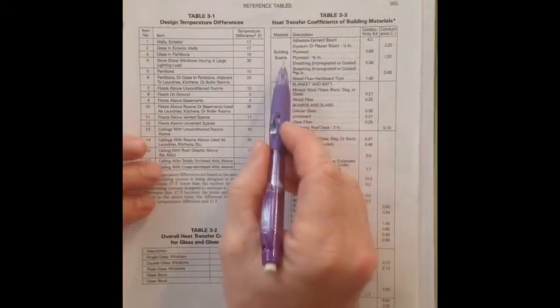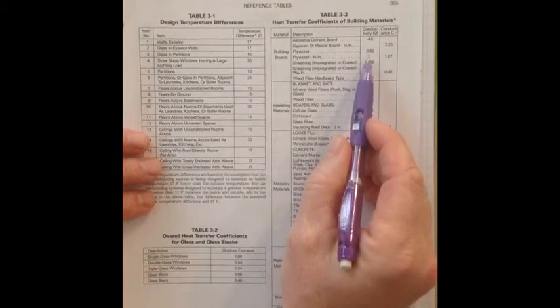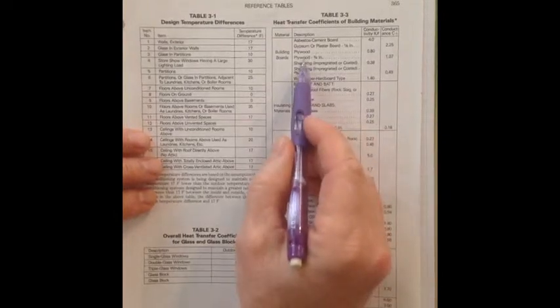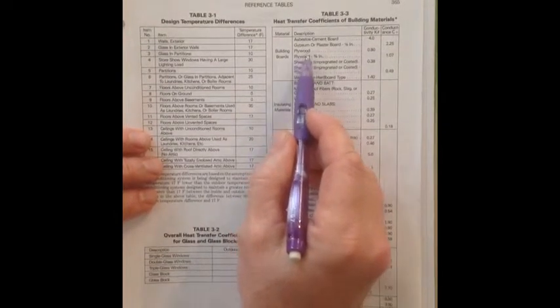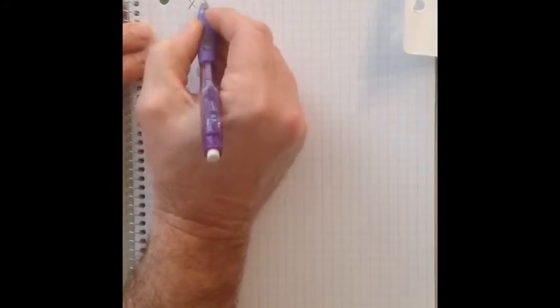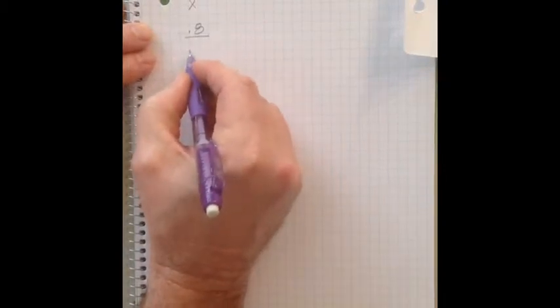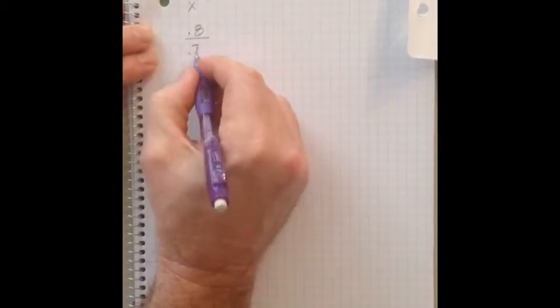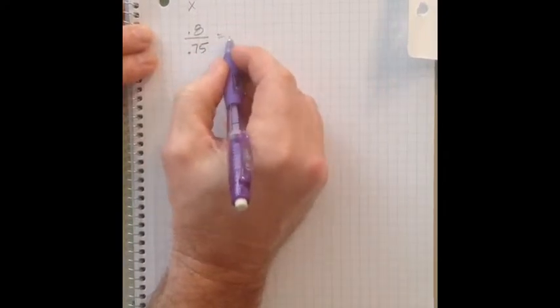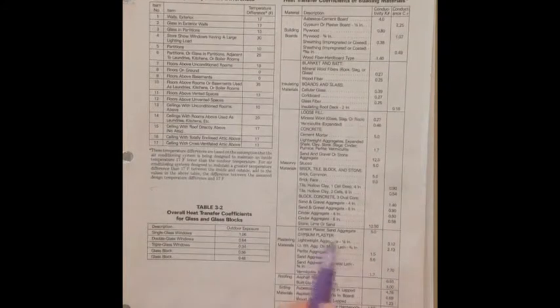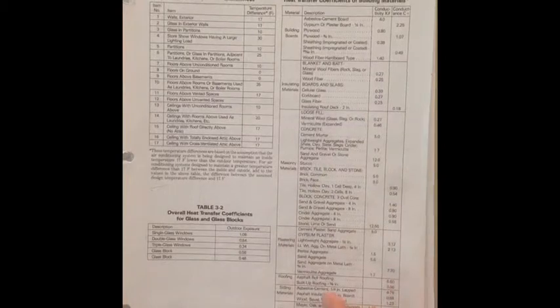So for instance, here in building boards, it says plywood has a K number of 0.8 and a C number of 1.07. Now the C number is for 3/4 inch plywood. The K number is just for plywood, no thickness applied to it. Remember, K over X, the K number divided by the thickness, equals C. We'll prove it here: 0.8 divided by 0.75, which is 3/4 of an inch, that's where the 3/4 came from, equals 1.07. So whatever the material is, if you divide the K number by the thickness, you will get the C number. Okay? Good.